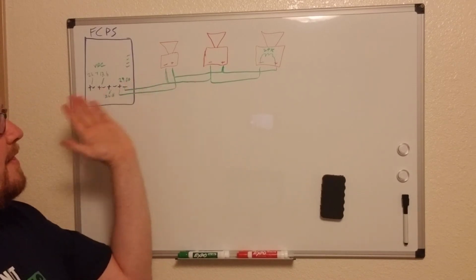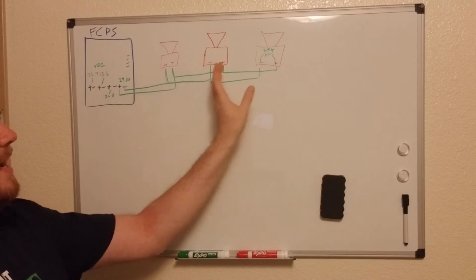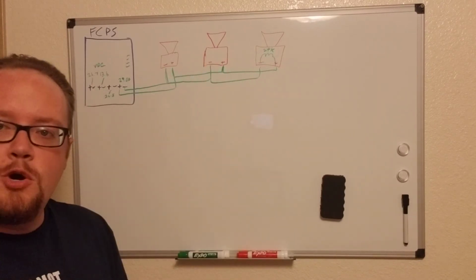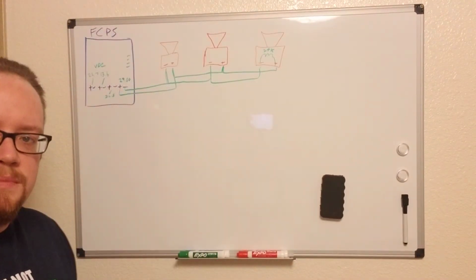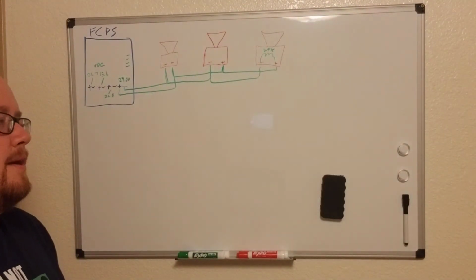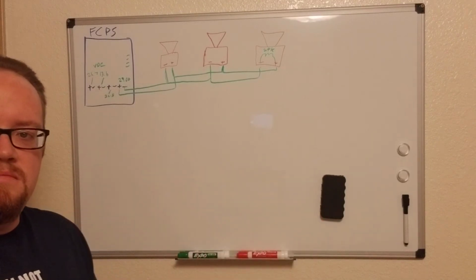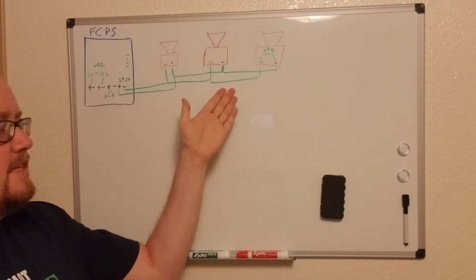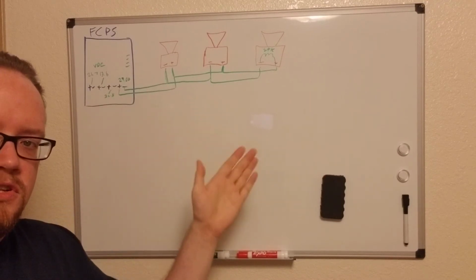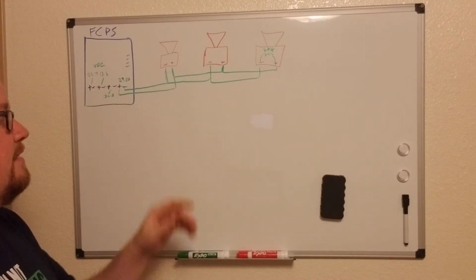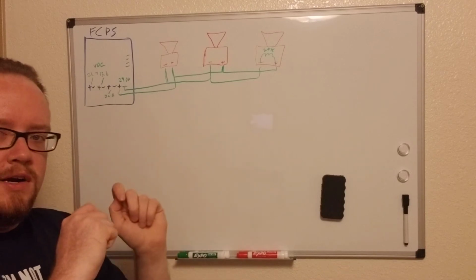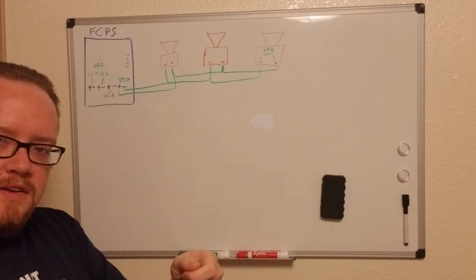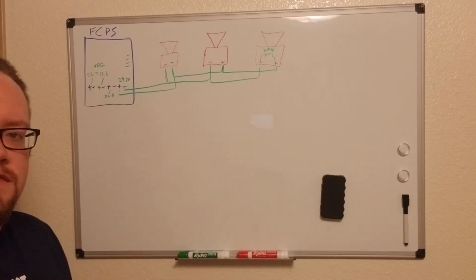This is what makes that method so great, is you can see the status of the circuit from the field side without having to go back and look at the power supply or look at the main panel, and you don't need a second person standing by at the front end. You can just see exactly what the status is from the voltage alone, and it's a huge time saver compared to yanking the wires off, separating the incoming and outgoing, checking for the end of line, seeing if you still want to check for end of line.